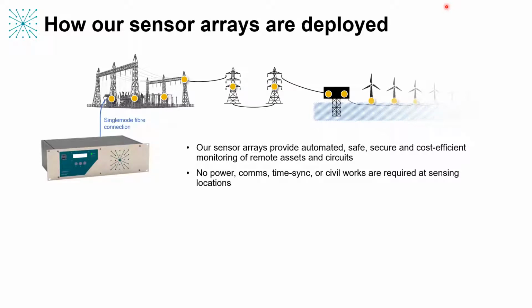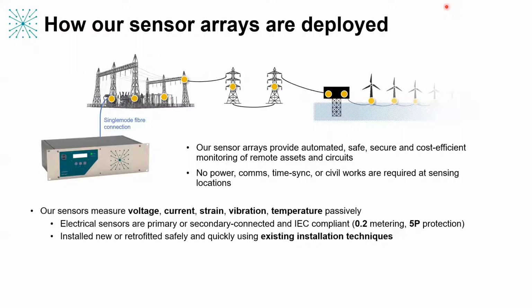The architecture of our sensor networks is generally the following. We have an active unit that we call the Interrogator, which is the only powered unit in the whole sensing system scheme. And it takes traditional DC power, it takes a time sync signal. The key aspect is that that connects to one of the fibers that go into the conductor, and then it can reach out from that point over 100 kilometers to gather in measurements of voltage, of current, of strain and vibration, or of point temperature of an asset. So we can mix and match any of those electrical and mechanical parameters. We pick them up at remote locations and bring that data back to the central point, traditionally in the substation, where we make use of it.